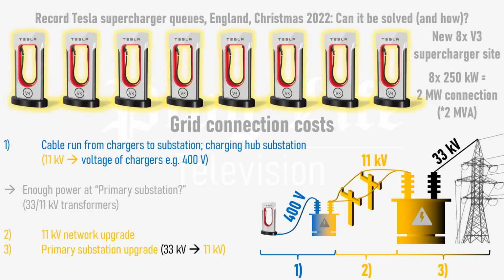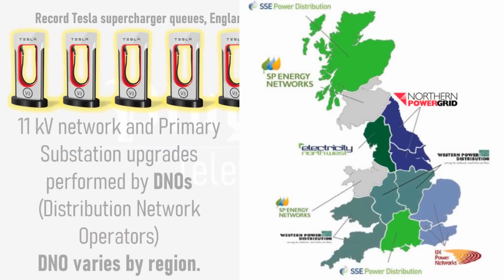The responsibility for upgrading the 11 kilovolt network and primary substation falls to the Distribution Network Operator, or DNO. Britain has many different DNOs that each look after a different region of the grid. You can get independent DNOs as well, they can do much of the work for you, but the DNO ultimately has to connect you to the grid in the end.